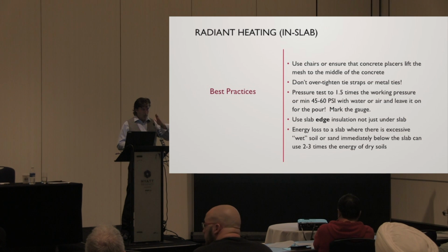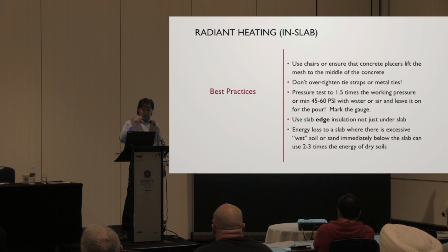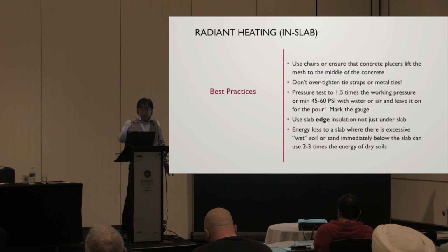I won't go into that detail, but when you tie this stuff down, obviously you want to have your tie wrap on the side and you want to snip it. Make sure you put it on the side, because as the guys come along, that zap strap is going to stick up probably half an inch off the top of the pipe, and that's a half an inch that could potentially poke through the concrete. So put it off to the side, don't tighten the heck out of it, and snip it off. Simple as that. Leave some looseness there.